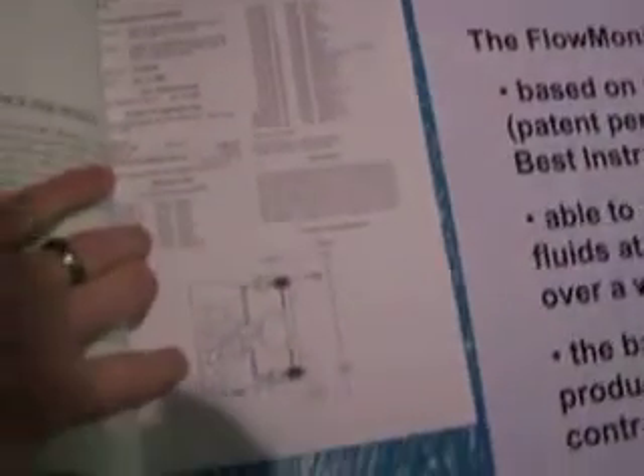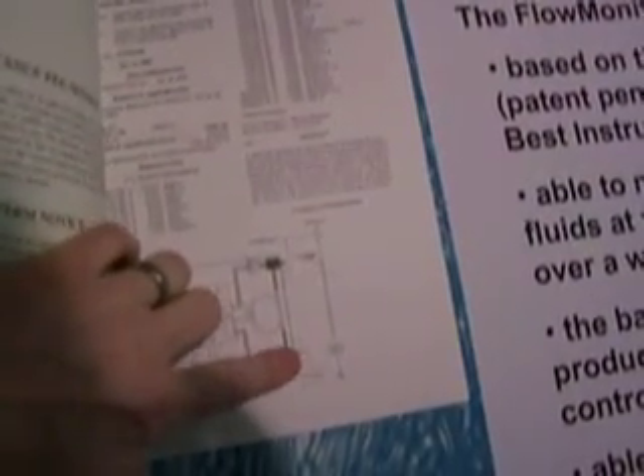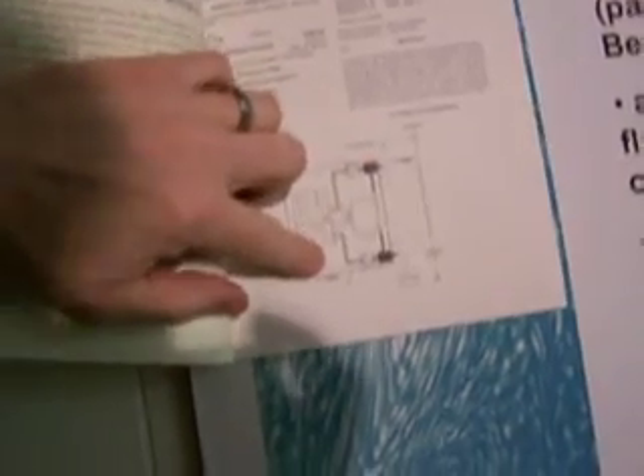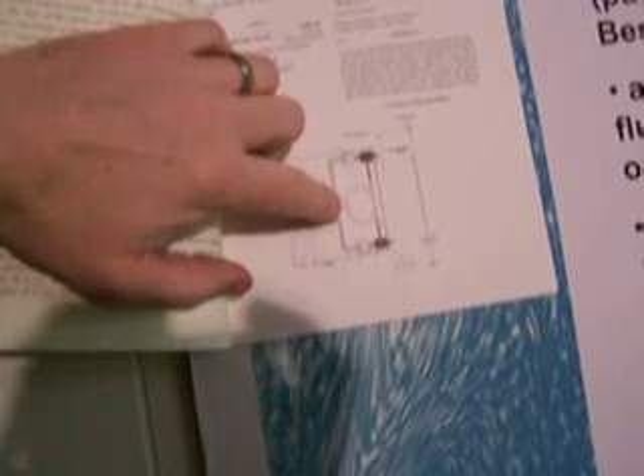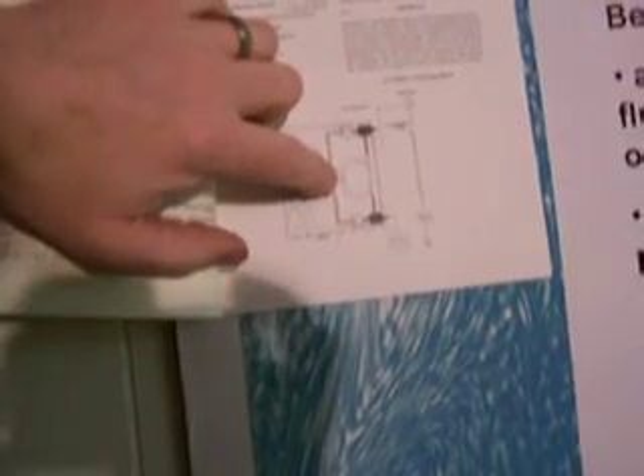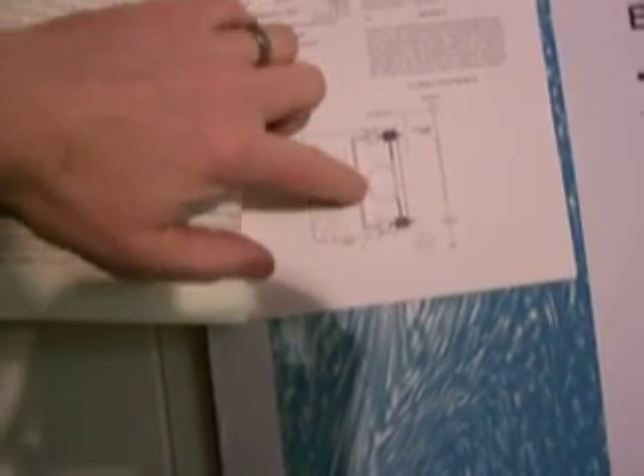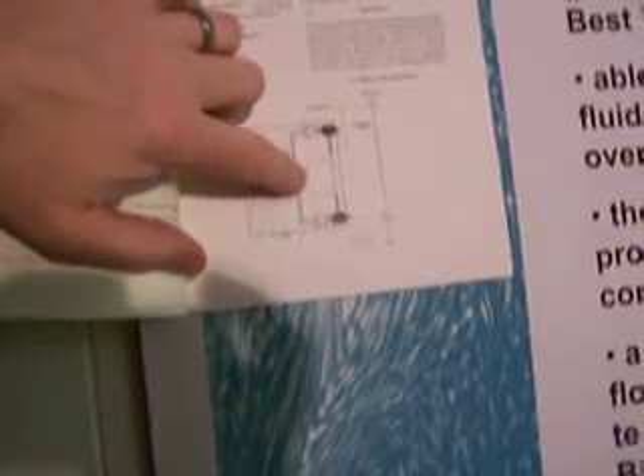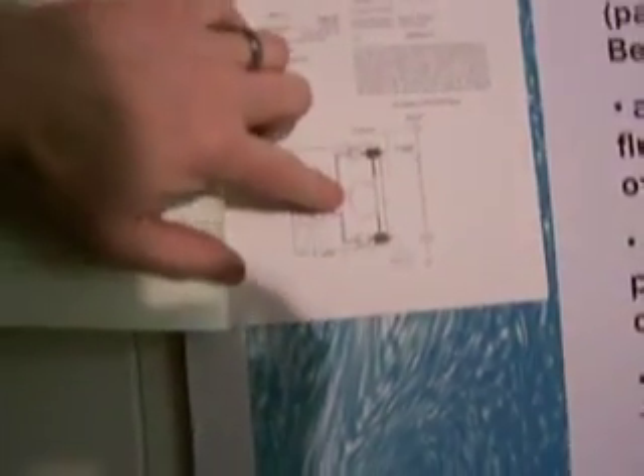When we look at the patent, we see here a schematic version of the unit where we have an HPLC pump feeding the manifold, the tubing over which pressure is developed, the output manifold, and here we are feeding a sample injector and an HPLC column. This basic block diagram can be embodied very cheaply. It's 2 pressure transducers and a thermistor or thermocouple, which is thermally coupled to an isolated loop of tubing, or a small straight piece of tubing, and the diameter and geometry can be configured for various flow rates.